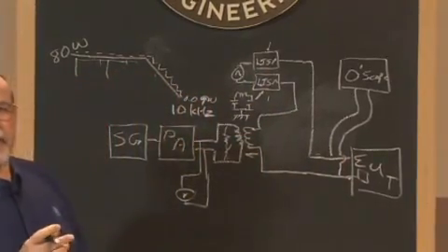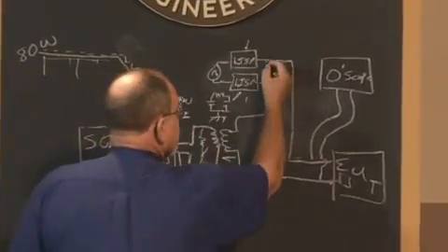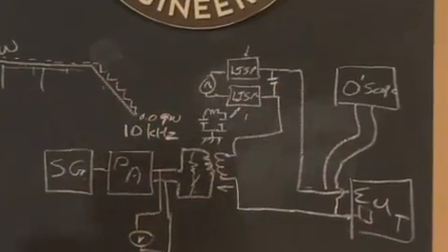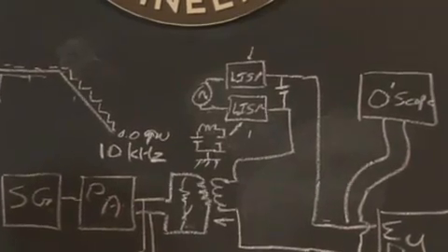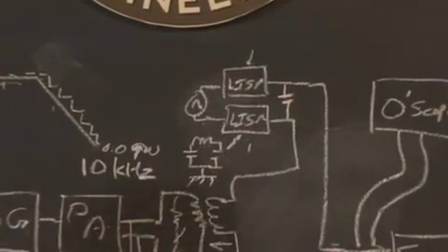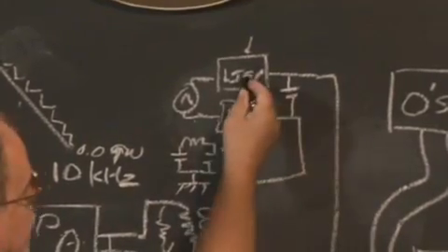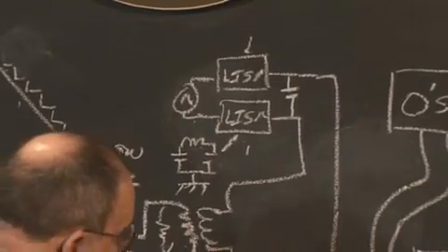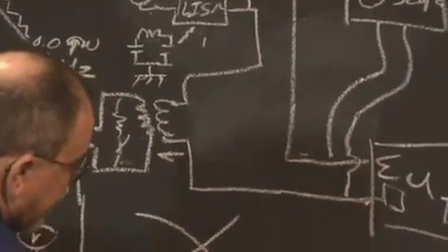So I need to be able to control that element. The standard calls for putting a 10 microfarad capacitor across those leads. It is absolutely critical that you do that or you're measuring incorrectly. This capacitor provides a short circuit as the frequency increases. So as the LISN's impedance is going up, the capacitor impedance is going down.